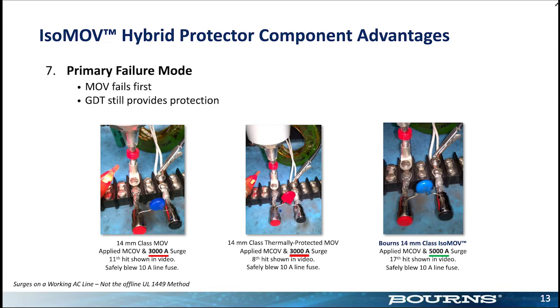The device did not get hot enough over a long enough period of time to melt that fusing element. It has the same problem that a normal MOV does. It's just blue. And on the IsoMOV, the last one, maybe you saw a little pinhole on the left-hand side. So if you would open that up, you'll see that the failure mode was not a pinhole type of a failure mode.